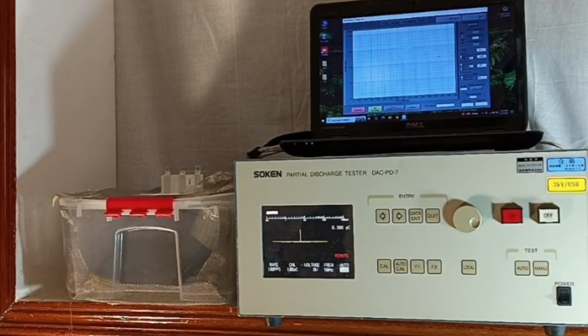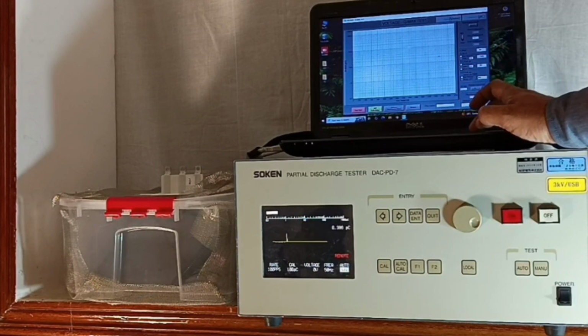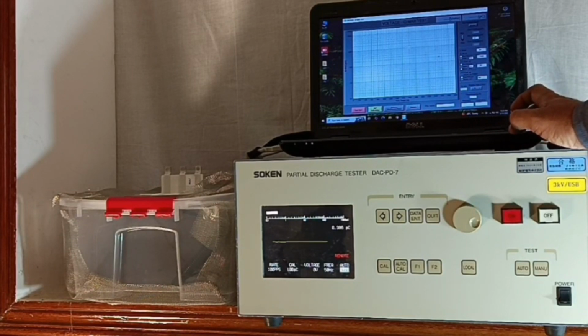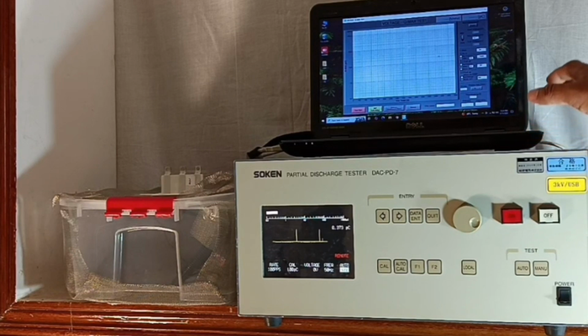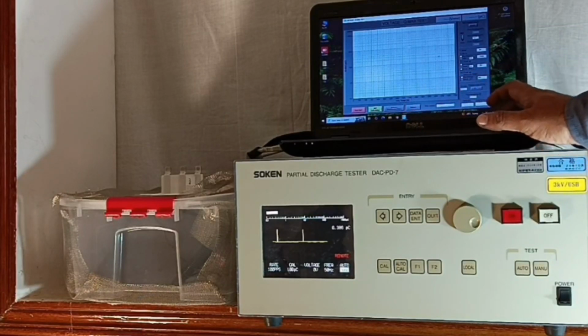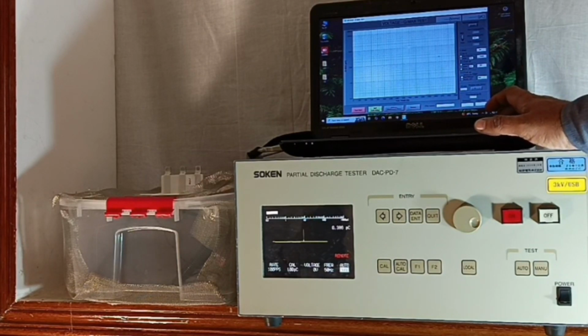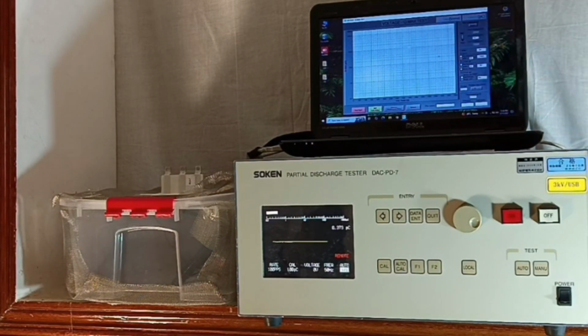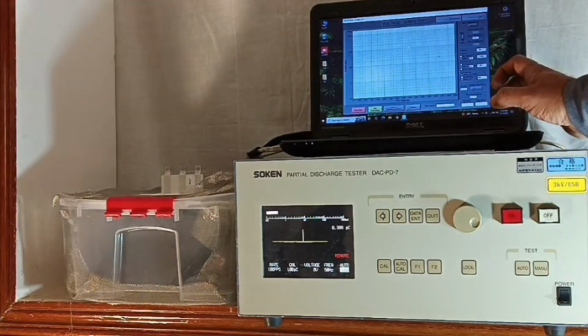Partial discharge measuring setup from SOKEN Electric Company Limited, Japan. The model DAC-PD-7, the partial discharge tester, is the standalone meter with the source built in, with the coupling capacitor and the PD pulse calibrator, all integrated in one unit. This uses the conventional measuring method as per IEC 60270. The meter and the source, the coupling capacitor, are rated up to either 5 kV or up to 3 kV based on the model requirement.